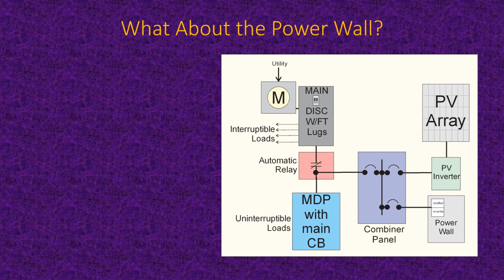Another question: can you supplement the PV array with a small fossil fuel generator when the sun's not shining for several days? The answer is yes. See that combiner panel down there? That's where you put another circuit breaker, and you have to have simply a lockout such that the generator and the utility can never be on at the same time. The other thing is you need to be very careful that the generator and the PV are not on at the same time. Why would that be? Simply because if the PV is meeting all the needs of the loads and there's excess PV looking for a place to go, if the generator is connected, it will try to run the generator backwards, and the prime mover of the generator is not happy when a PV system tries to do that. So it's very important.